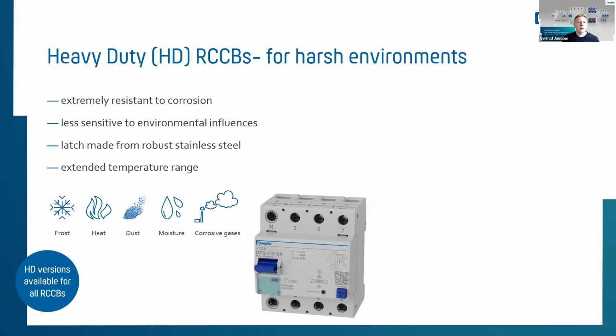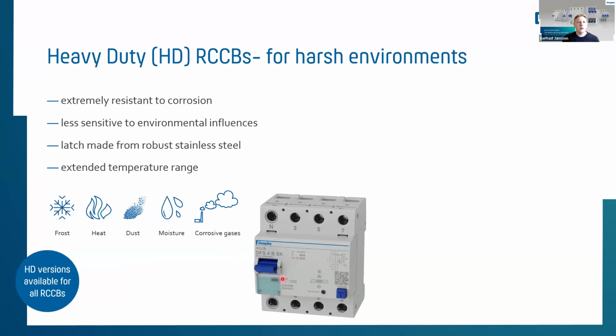They are made of different materials, so they are extremely resistant to corrosion. They're less sensitive to environmental influences like frost, heat, dust, moisture, or corrosive gases, for example. The tripping latch, which is underneath here, is made from special stainless steel to avoid corrosion. And it even has an extended temperature range. We are able to go up to an ambient temperature of 70 degrees Celsius. The standard is normally -25 to 40, and with this special HD version, we can also cover applications up to 70 degrees ambient temperature.